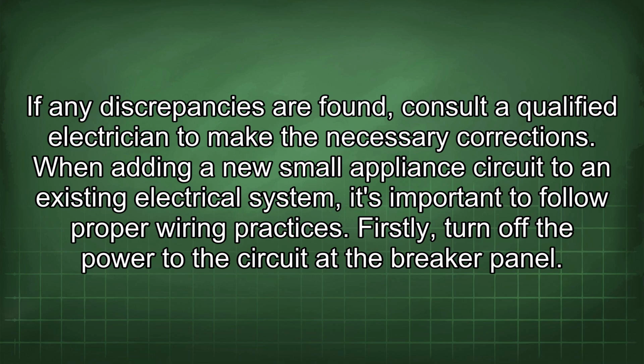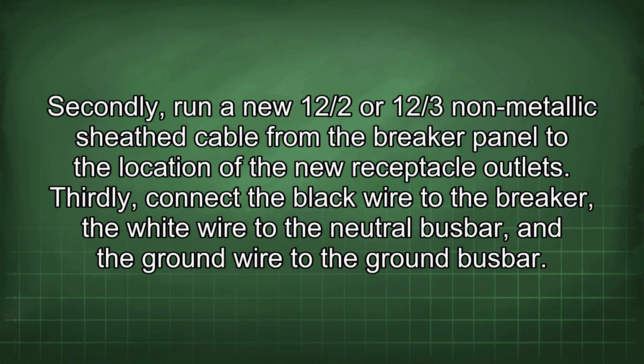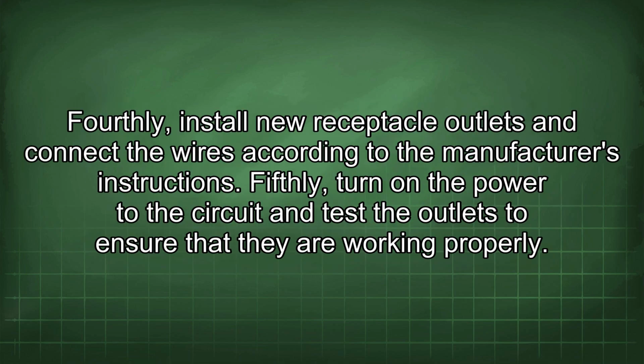When adding a new small appliance circuit to an existing electrical system, it's important to follow proper wiring practices. Firstly, turn off the power to the circuit at the breaker panel. Secondly, run a new 12/2 or 12/3 non-metallic sheath cable from the breaker panel to the location of the new receptacle outlets. Thirdly, connect the black wire to the breaker, the white wire to the neutral busbar, and the ground wire to the ground busbar. Fourthly, install new receptacle outlets and connect the wires according to the manufacturer's instructions. Fifthly, turn on the power to the circuit and test the outlets to ensure that they are working properly.